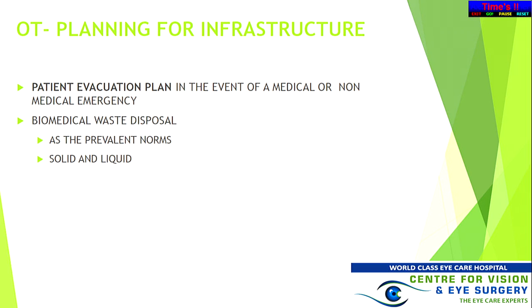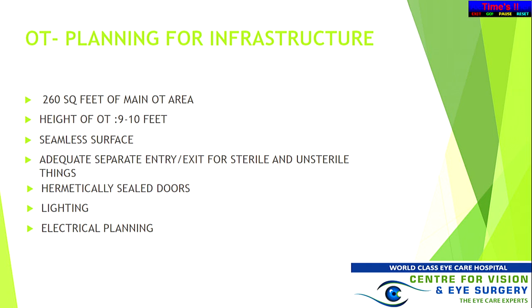In terms of infrastructure, 260 square feet of main OT area is compulsory, with a height of 9 to 10 feet. You need a seamless surface, adequate separate entry and exit points, and hermetically sealed doors. Lighting and electrical planning I've already touched upon.